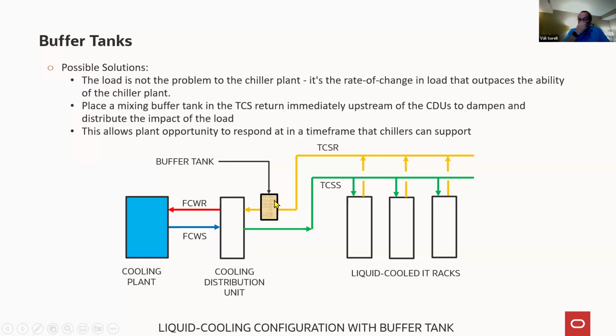The biggest reason for doing that is to slow the response so the chiller can keep up with it. The chiller will typically, if it's operating, respond to a load in maybe a minute. If the chiller is not on, you have to start it up. It may take 2 minutes to start up, maybe a couple more minutes to come to full production. So if I can hold off the load as it hits the chiller plant, I have in essence been able to eliminate that possibility.